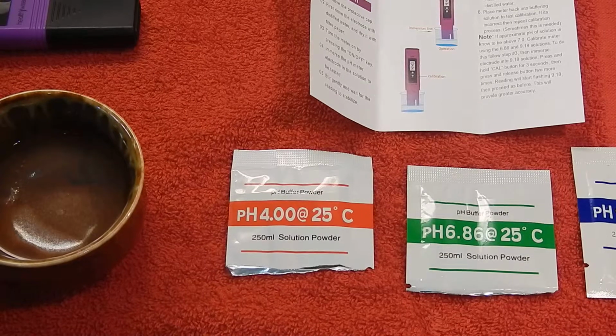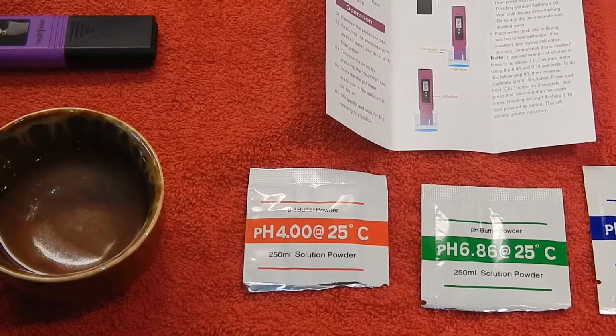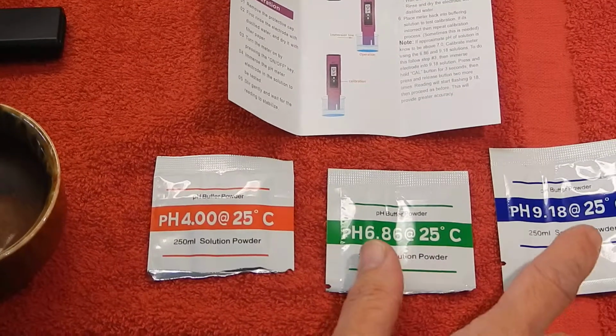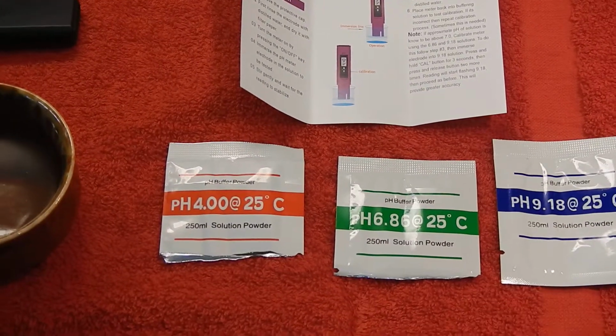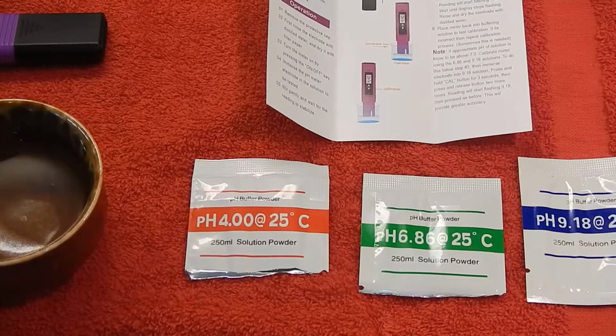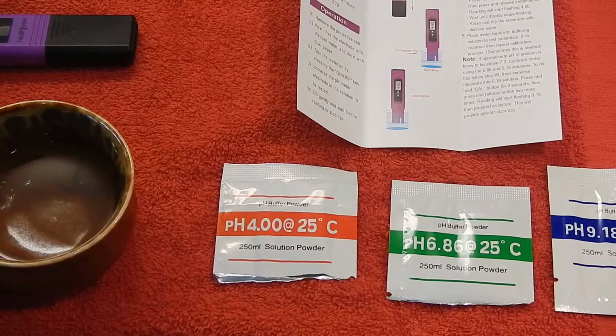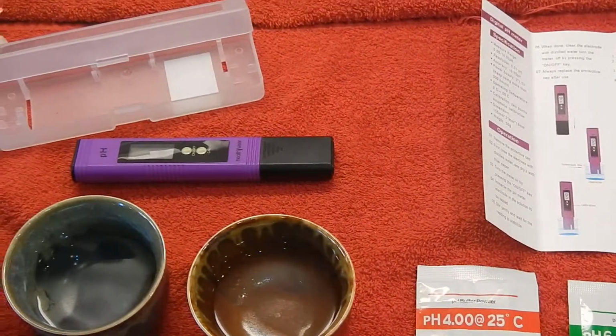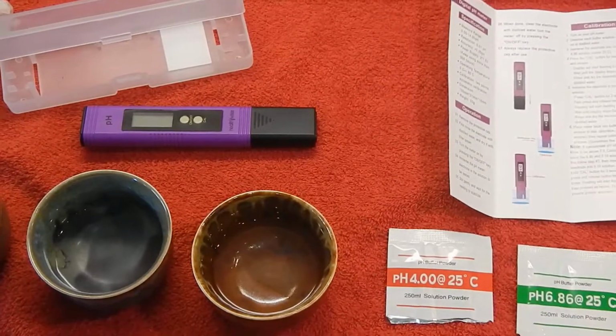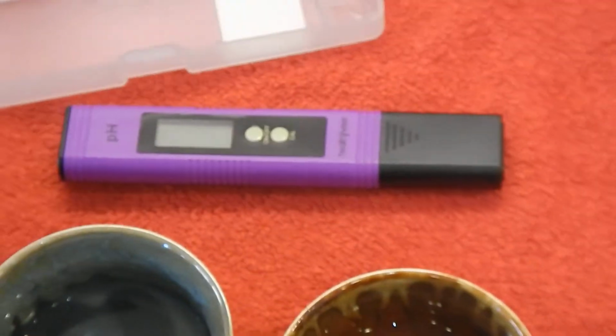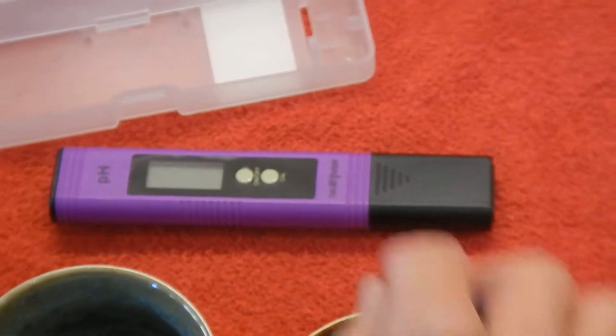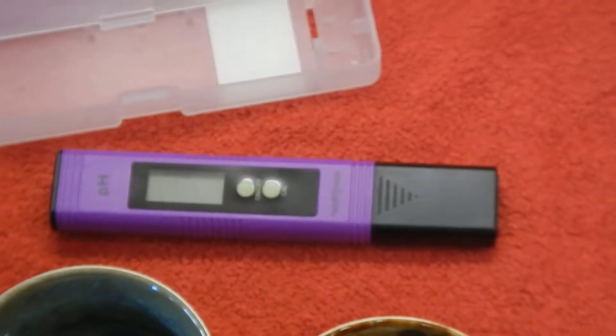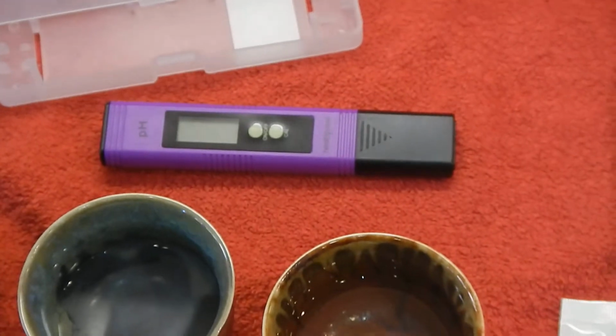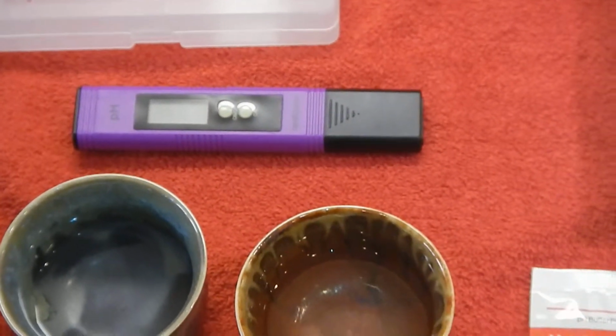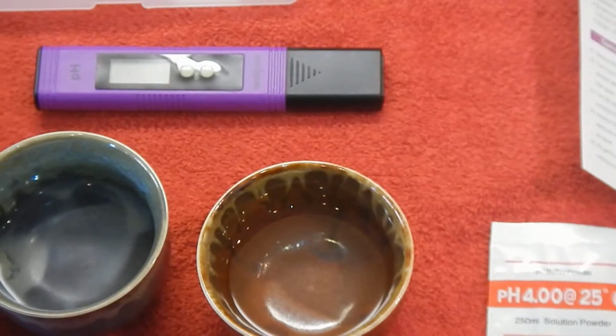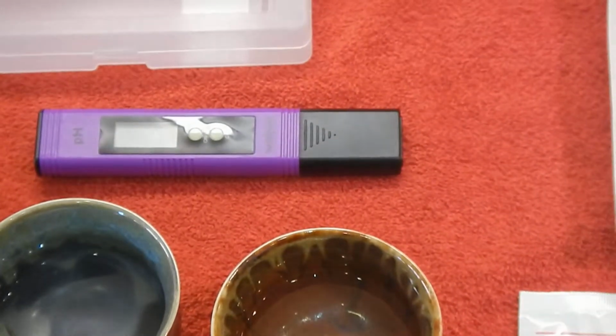Now, if you know you're going to be testing a solution that's pH 7 or higher, you repeat the calibration procedure, but now use the 6.86 and the 9.18. And you will want to recalibrate not only before the first use, but also if you're looking for really high test accuracy, you have a requirement that needs it to be very accurate, or if you have a large period of inactivity, or if it's been used frequently, or if by mistake you press this calibration button and expose the electrode to air. Other than that, like I said, it's really easy to use. It's very, very useful, and it gives you peace of mind to understand the pH level of various liquids that you're using every day in your household.